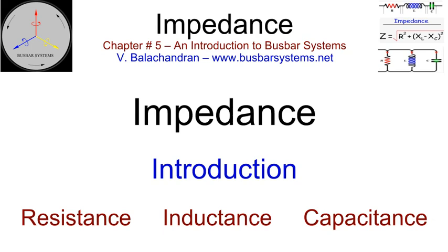In an AC circuit, the steady-state current will be proportional to the applied voltage and depends upon resistance, inductive reactance, and capacitive reactance. Inductive reactance is proportional to the frequency, while the capacitive reactance is inversely proportional to the frequency. Resistance is frequency dependent. These three parameters are most crucial in the design of busbar systems, as they quantify and help in keeping the constraints imposed by the specification on temperature rise, power loss, and voltage drop, or a selected combination of the three.